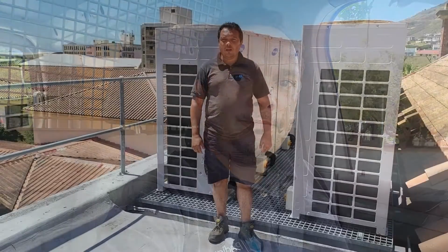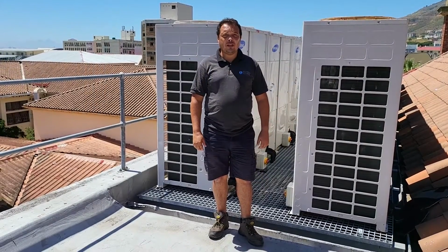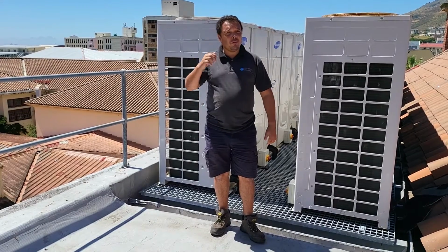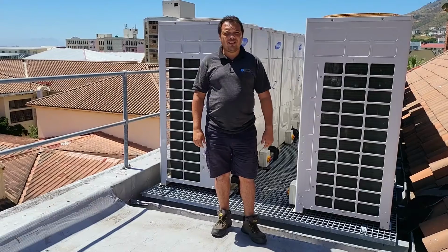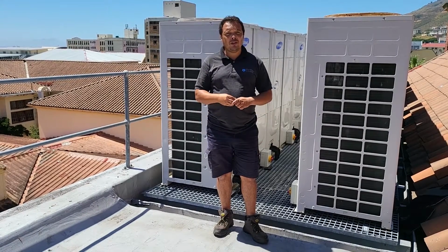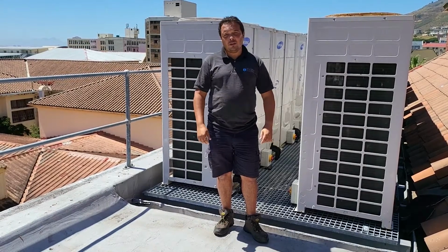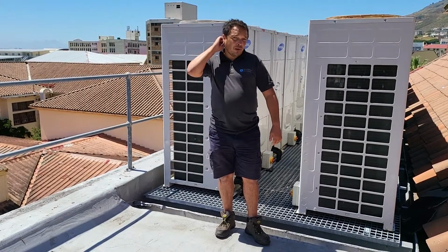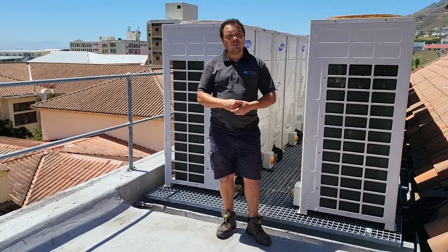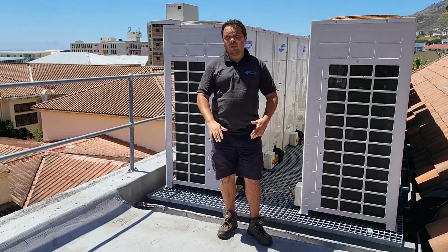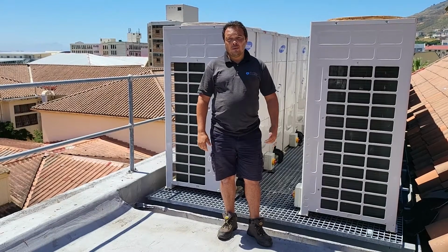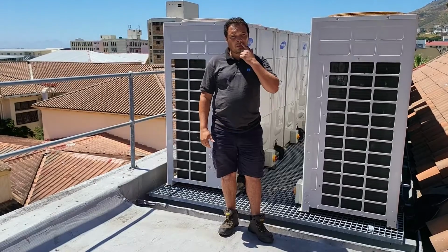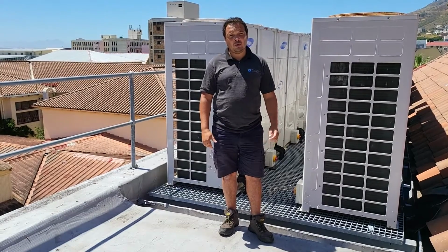The site they've asked us to look at is the Cape Town Magistrates Court. They've been having ongoing issues with these systems over the years. There were apparently issues with some contractors with the installation, and as a result they've been having constant issues with these types of error codes related to the installation. The 215 and 213 error codes the client has communicated to us are consistent with, well, the 213 error code says that the addressing on the MCUs is not matching the addressing on the indoor unit.